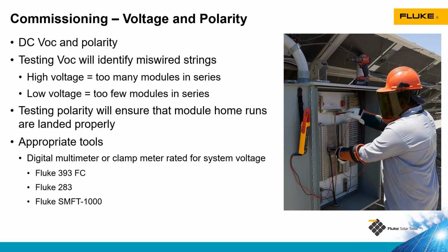Now, the 393 clamp meter, when it sees reverse polarity, you get the negative symbol, it says polarity on the screen, the entire screen lights up red, and it beeps at you. So it's basically impossible to miss a reverse polarity situation with that meter.